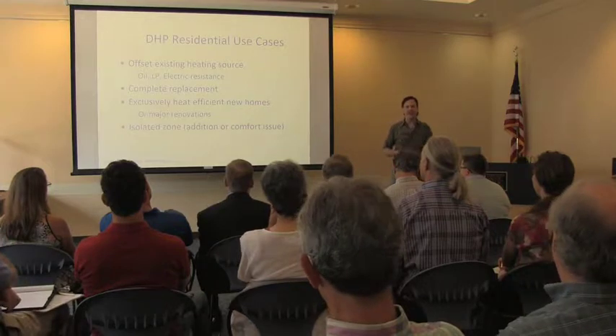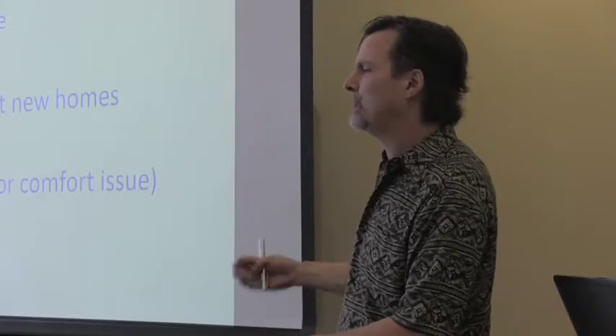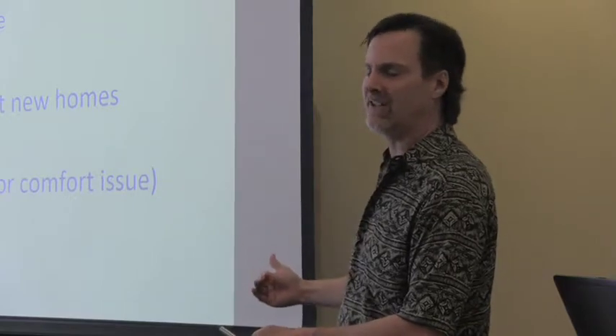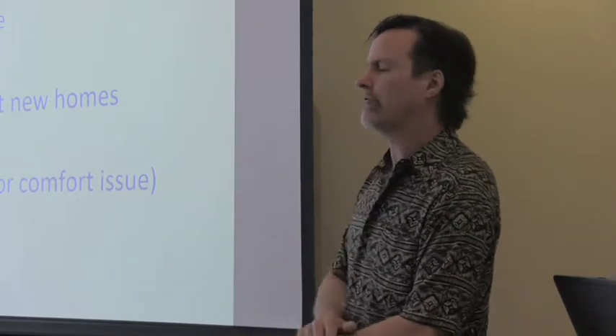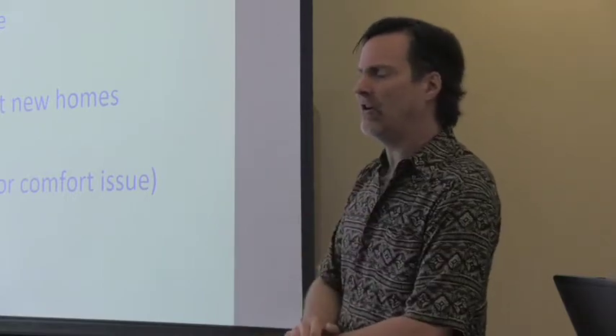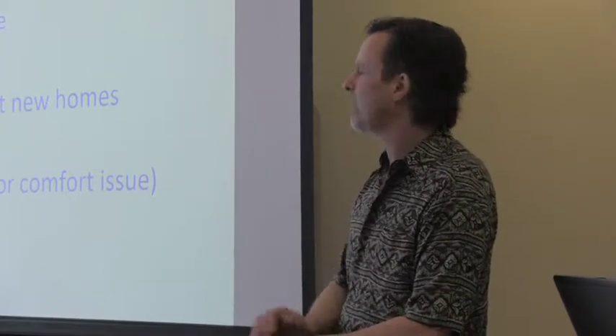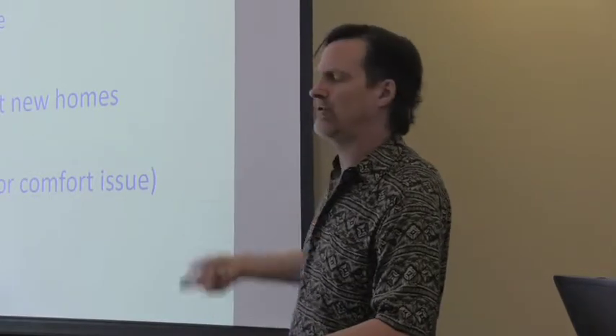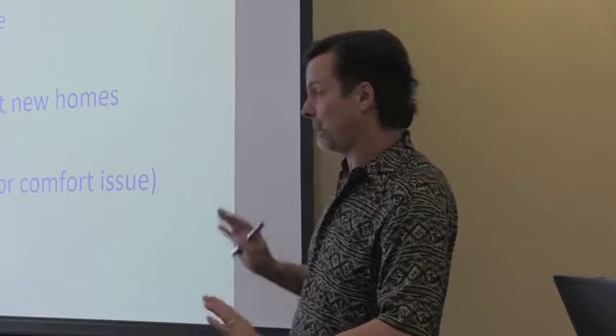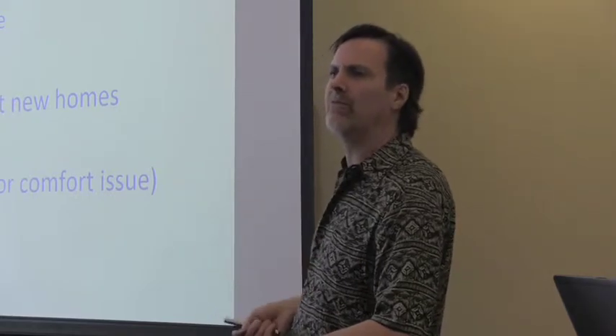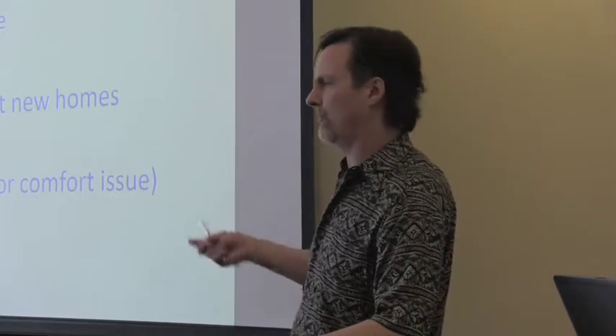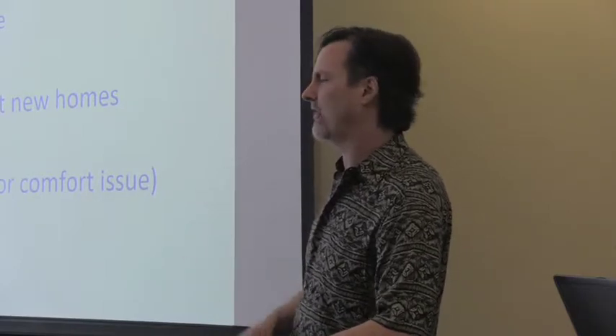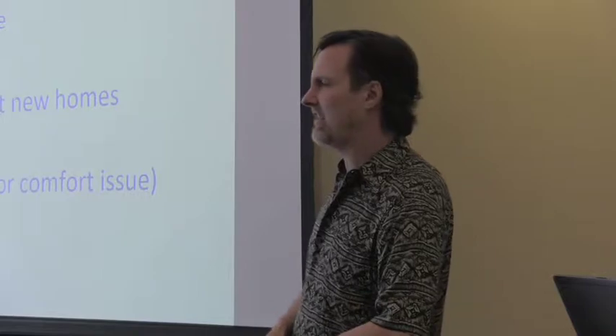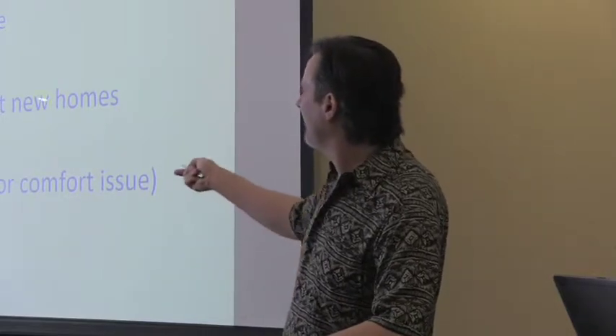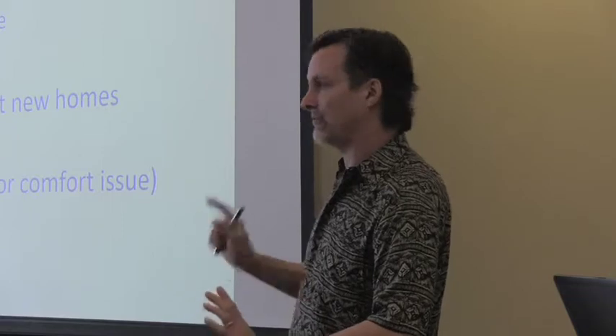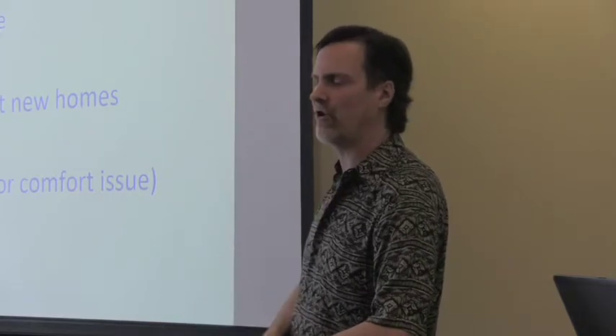Even new homes that are built to code today, minimum code, the energy standards for minimum codes are so much better than they were even 5, especially 10 or 15 years ago. The actual heating load of a typical new single family home is so small that you really only need probably two or three zones. And these are a very, very good match for low energy homes. New construction programs like Energy Star or LEED for Homes, or even the more advanced low energy design like Passive House, it gets very, very easy to heat these homes with a very small air source heat pump.